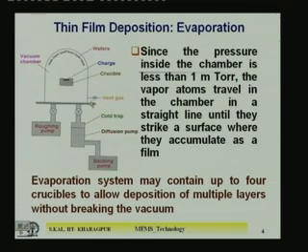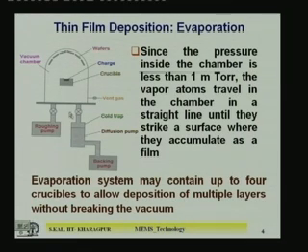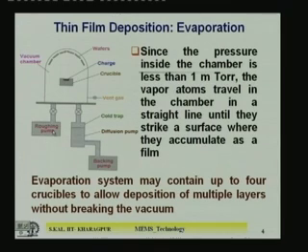There is a vent gas. Venting is required when you want to bring the chamber back to atmospheric pressure — you introduce some gas so that inside and outside pressure are equal, then you can open the bell jar and take out the substrate. That is why a venting mechanism is needed. The pressure inside the chamber should be very low — one millitorr or less — for getting uniform deposition of metal or any material on the surface. You need high vacuum.